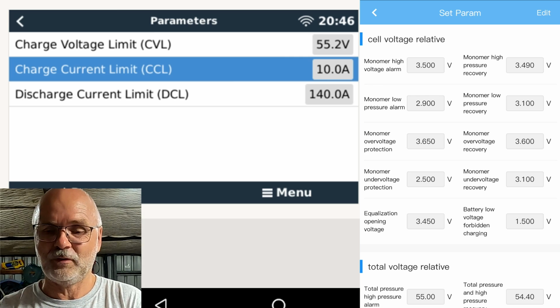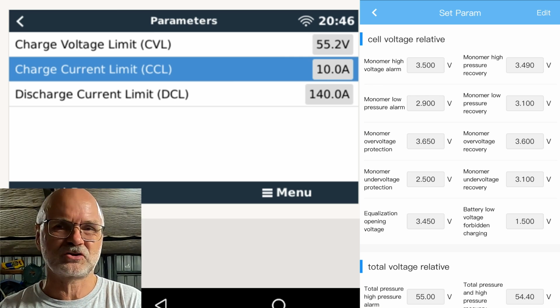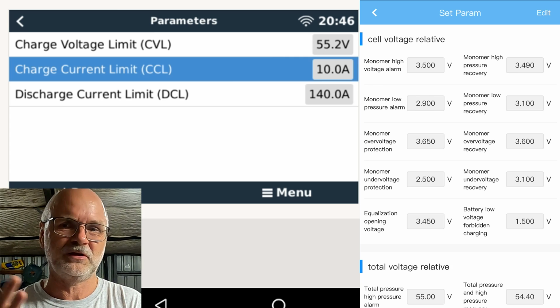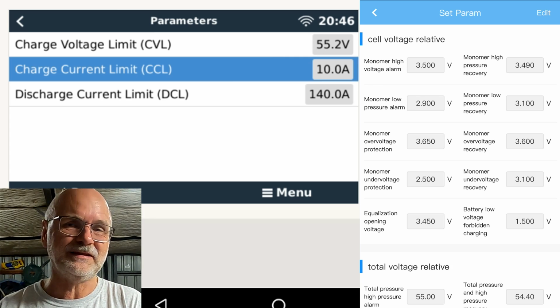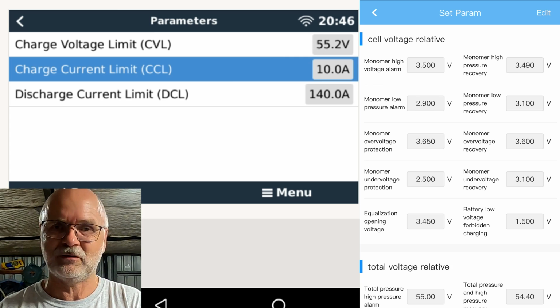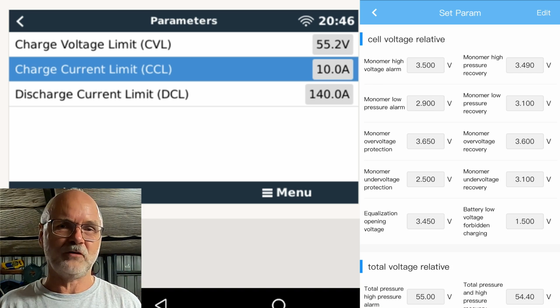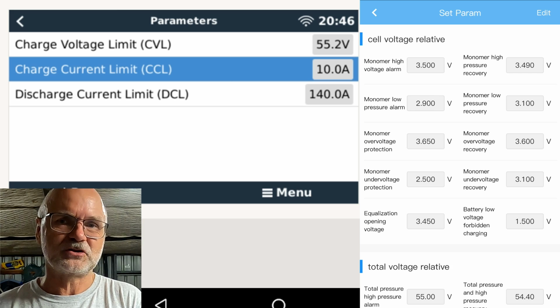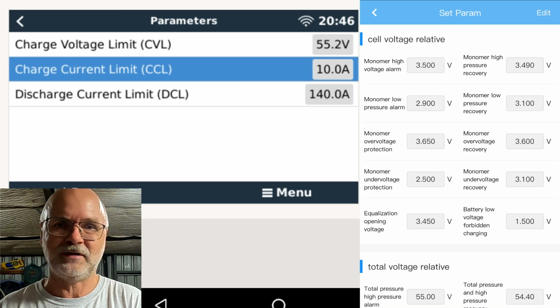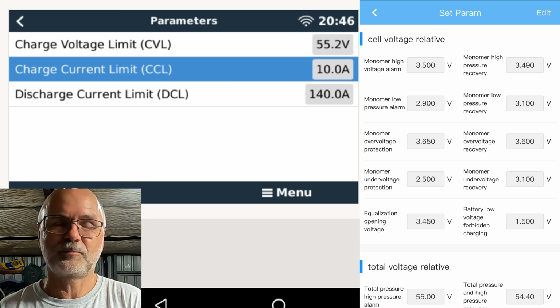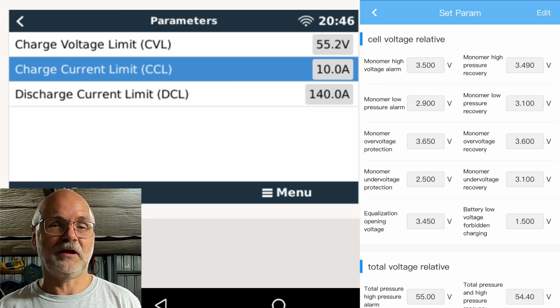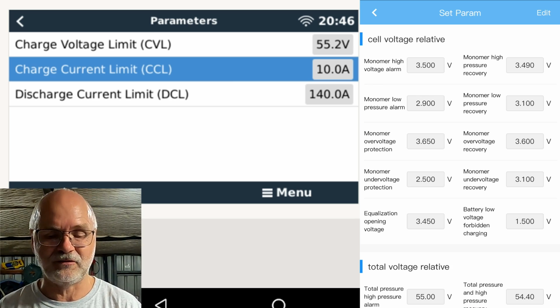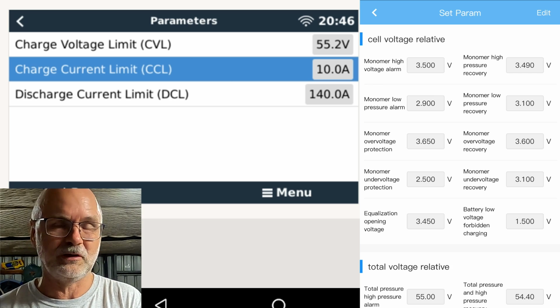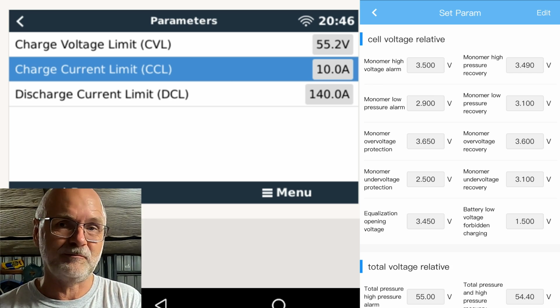And you want to ask, well, why do you want to limit the charge current? You want to charge as much as possible into your battery. Well, if you have a lead acid battery, an AGM battery, or any flooded battery still, and you have a very large solar array system, you cannot just charge your lead acid batteries with an unlimited current. Usually these batteries are charged with 0.2 C only. And depending on the size of your battery bank, then you have to limit the charge current. Otherwise you will overcharge, you will damage your lead acid batteries.